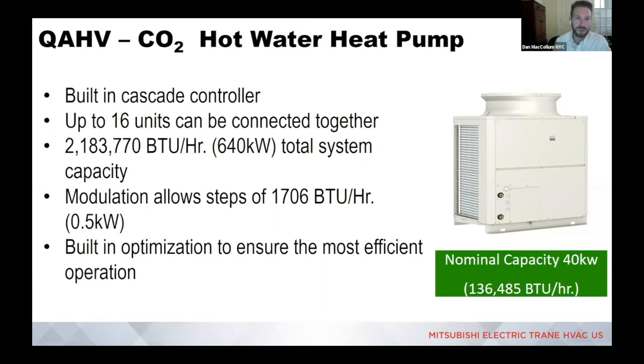What it's designed to do is it either targets a return air temperature set point or a space temperature set point, and then the fan speed, the refrigerant flow, and now the water flow all vary to meet that either return air temperature set point or space temp set point. So your leaving water temps are going to vary, and it's going to be a function of the distance from set point in that particular zone, the style of unit, the different airflow settings that unit has, or the airflow setting that you have it locked into. So that's a challenging question to answer, even just on a standard VRF system, but it's going to vary is the short version. Okay, thanks.